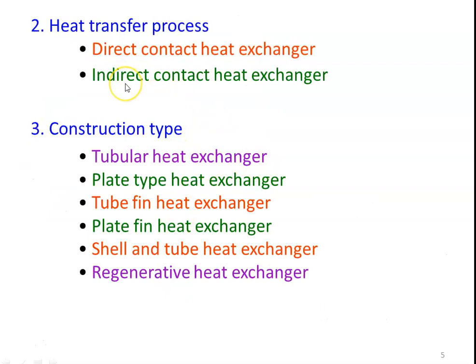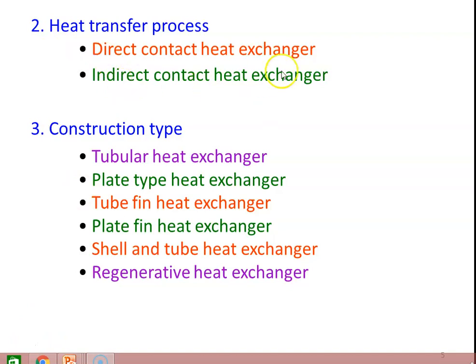Based on the heat transfer process, the heat exchanger may be a direct contact heat exchanger or indirect contact heat exchanger. In a direct contact heat exchanger, the hot and cold fluids mix directly — for example, mixing cold water with hot water. In an indirect contact heat exchanger, the hot and cold fluids are separated by a metal surface with no direct contact. All the heat exchangers we are going to design are indirect contact heat exchangers.